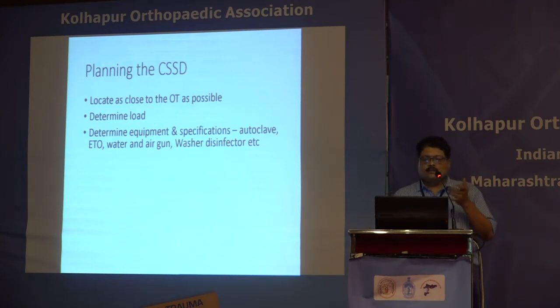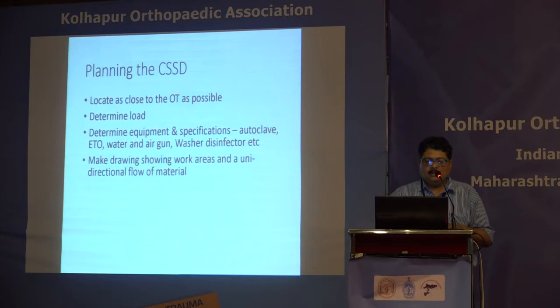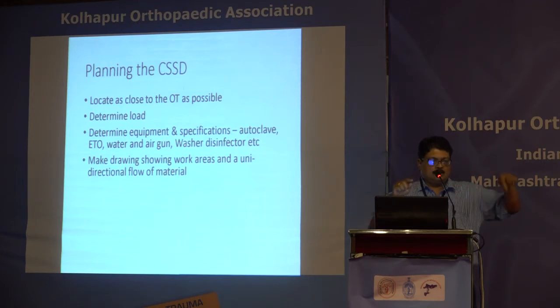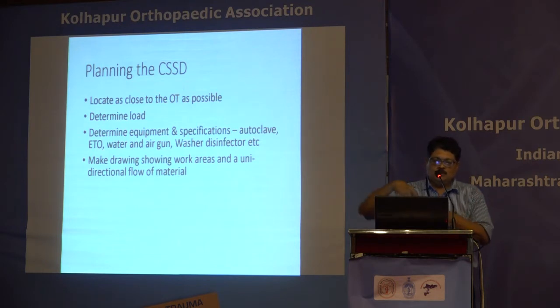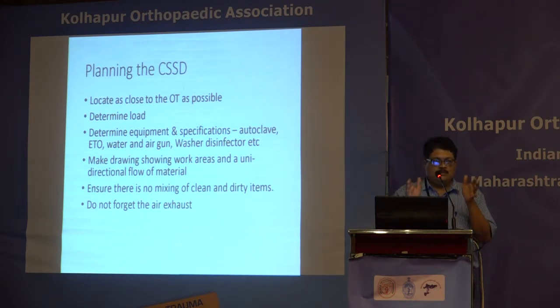Determine the equipment and specifications to handle the load — what size of autoclave is needed, and whether to use washer-disinfectors or ultrasonic cleaners. Define the equipment, specifications, and floor sizes. Then make a first drawing and verify that there is a unidirectional flow of material: anything that comes to the cleaning area should flow in one direction. Clean and dirty should never mix — this is what accreditation inspectors also look for.